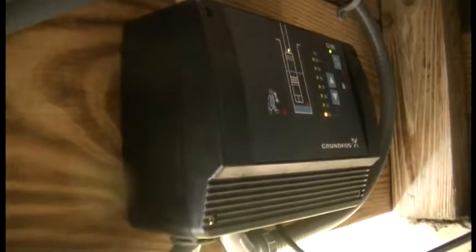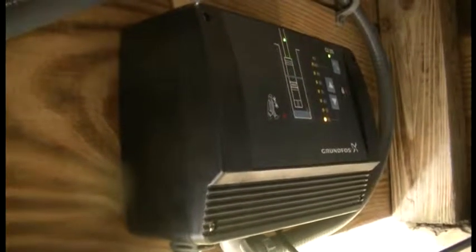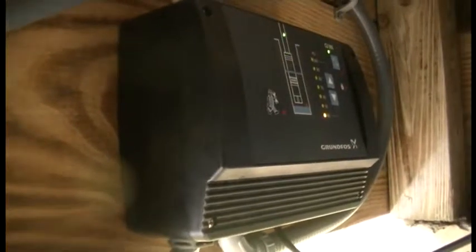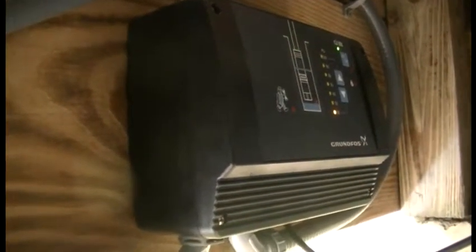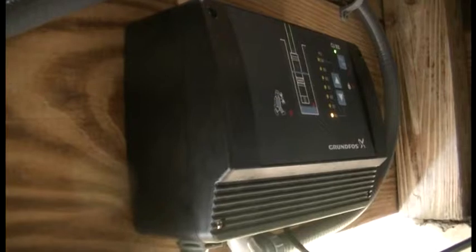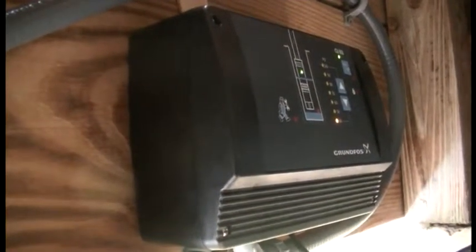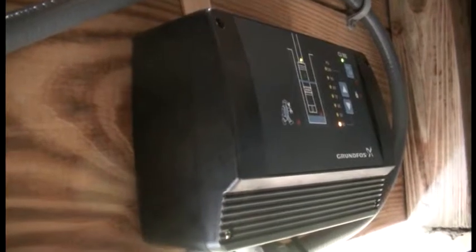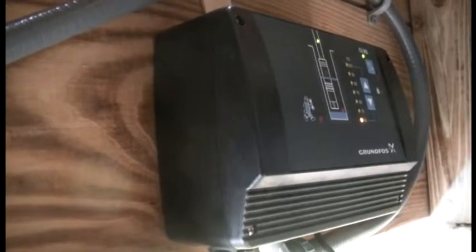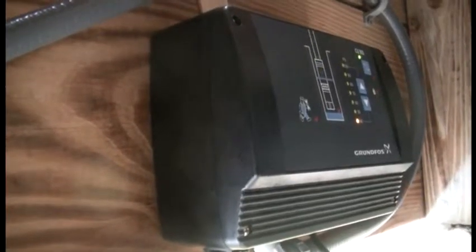And it basically is a very simple unit. It's very nice. Basically, you see a few arrows on there. You can set it to whatever pressure you like. These are often used in homes with just conventional water wells for their homes. And you can dial that to 60 psi, and your faucets will always have 60 psi, which is a nice feature. But for this geothermal system, it also works very nicely because it only runs the pump with enough power to provide the amount of cooling that's needed into the heat exchanger.